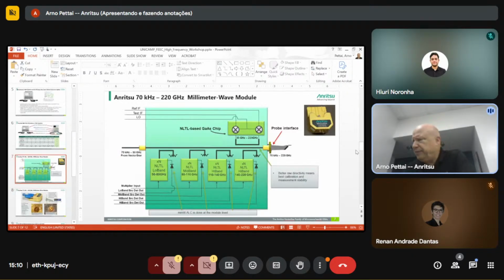So what's inside one of these millimeter modules? Well, there's quite a bit going on. It is a full reflectometer in a package that's basically the size of the palm of your hand. It's very small. Again, that's allowing us to move it very close to where our probes are, in most cases direct connecting to the probe. So that's a huge advantage.